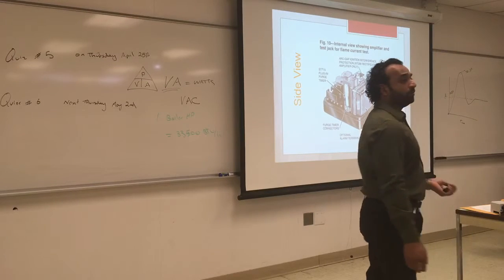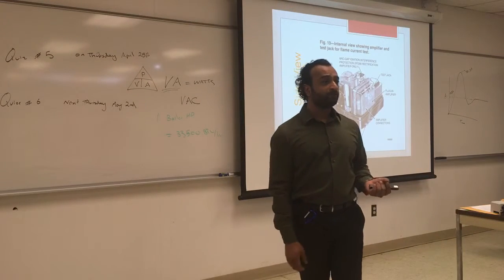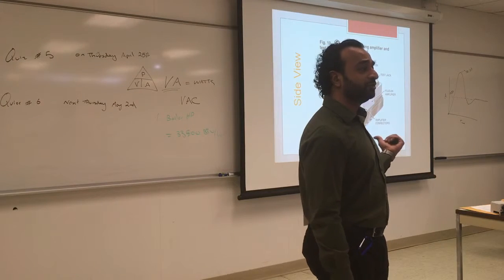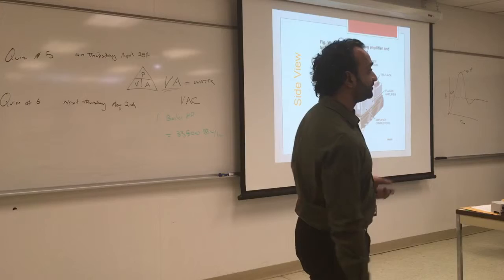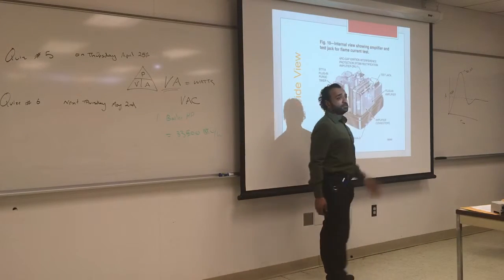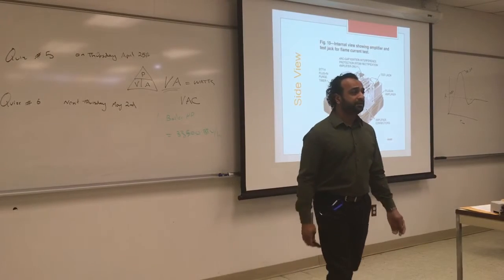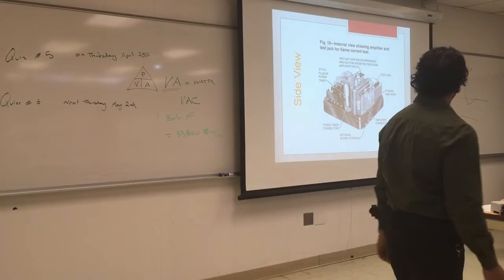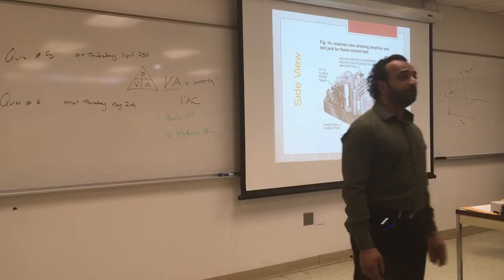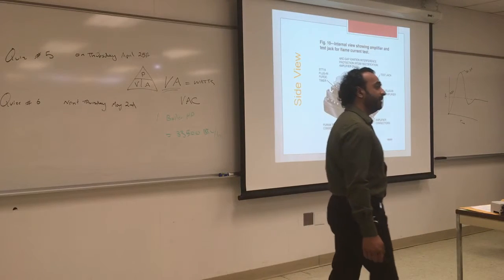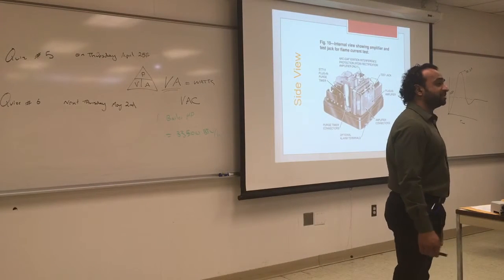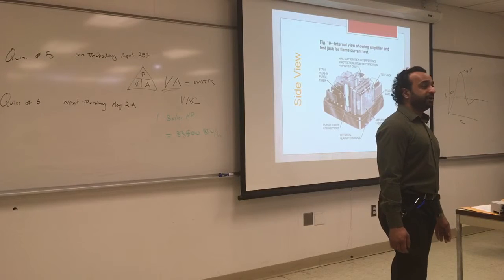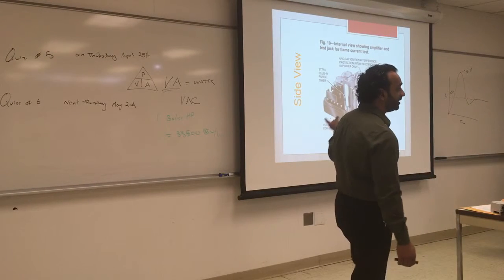Amplifier. So what would you do if you want to change the timing and the sequence of operation in any of those controllers? Change the amplifier or change the cartridge. Since these can be opened, at some point they require certain maintenance on the contacts of the relay. They say never clean the relay with paper or brushes. They have a special contact spray that Honeywell sells that you can spray the contact with.